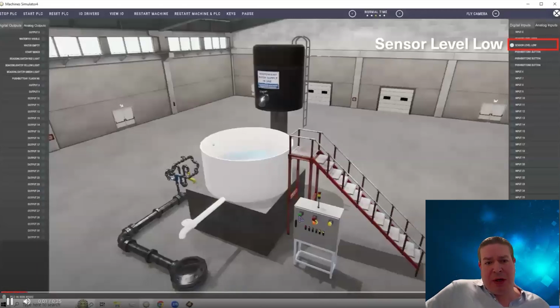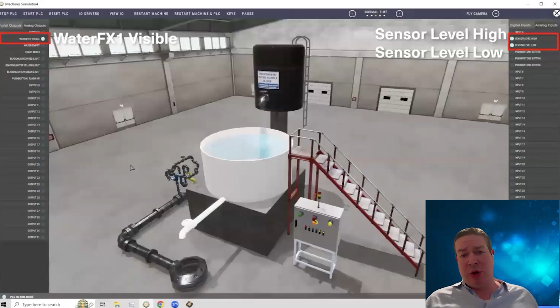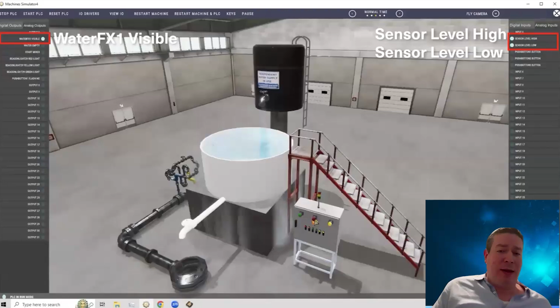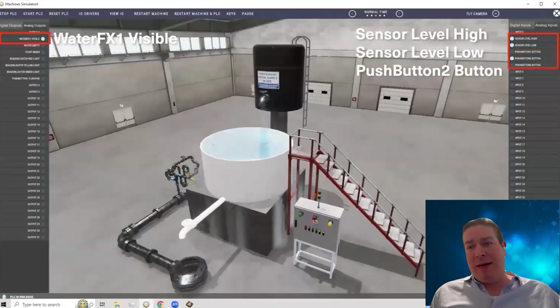So that's roughly what's supposed to happen here if this video plays properly. We hit the green button, it starts draining in, goes up, hits that sensor — the sensor doesn't trigger because there's no logic for it, and it proceeds to flow over. So if you're the operator and you go hit the red button like we're doing here, sure, it tries to stop it, but there's no programming within the PLC to do it.